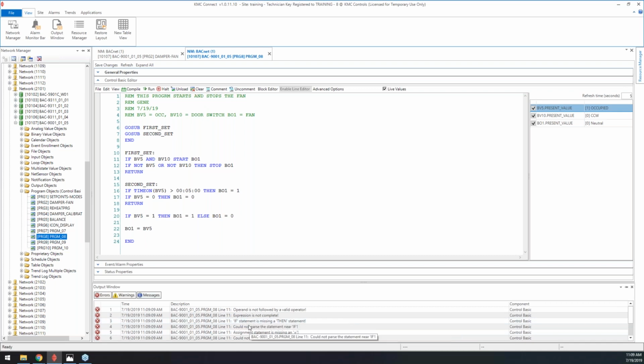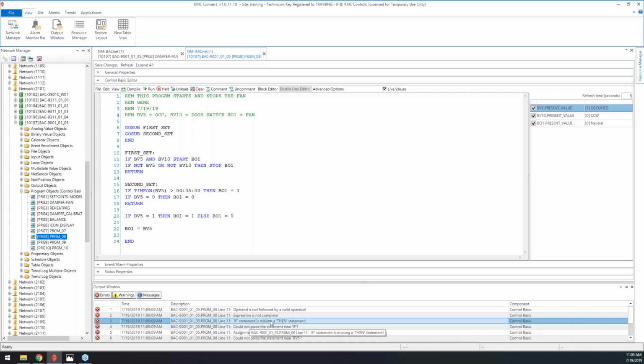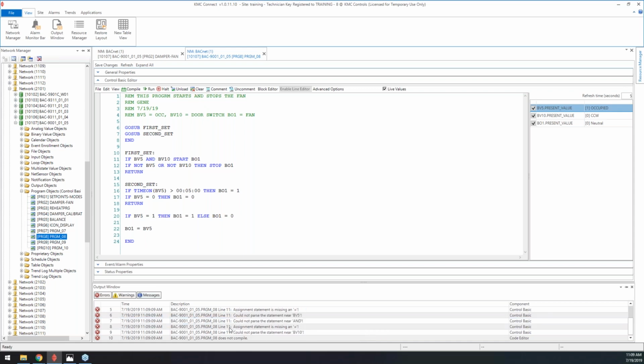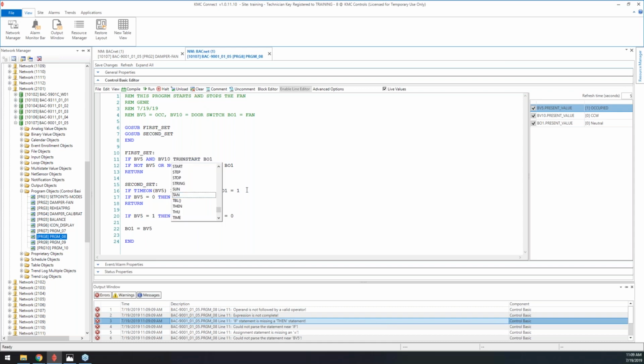So here we've removed that THEN reference, so the IF statement is not formed correctly. The compiler is going to chunk out a bunch of errors and say that something's not valid, and it'll give us a clue as to what's wrong. There's lots of references to line number 11, so that's where we want to look first, and then it'll give you a clue to either it couldn't find a keyword it was expecting, like THEN, or a variable wasn't referenced the right way, or a variable was referenced out of order. So removing that THEN statement, there's a few different errors in forming that line of code.